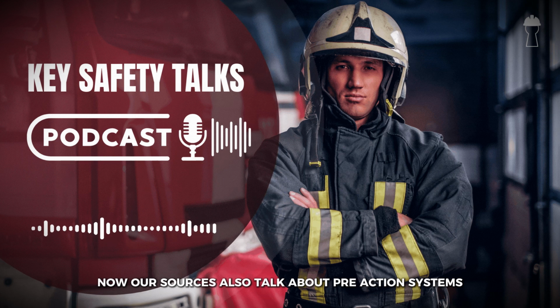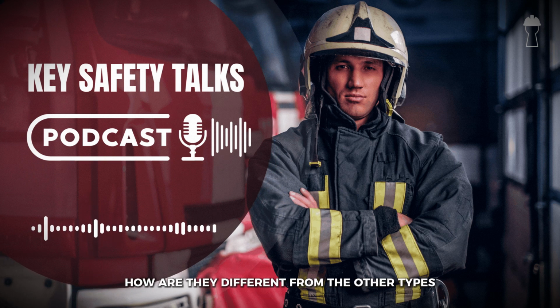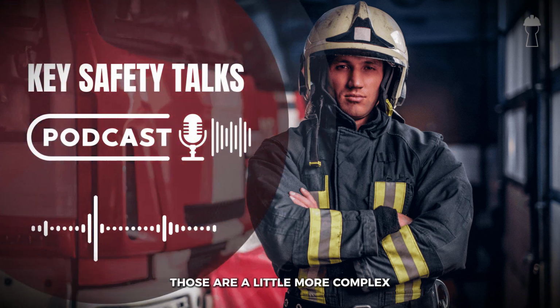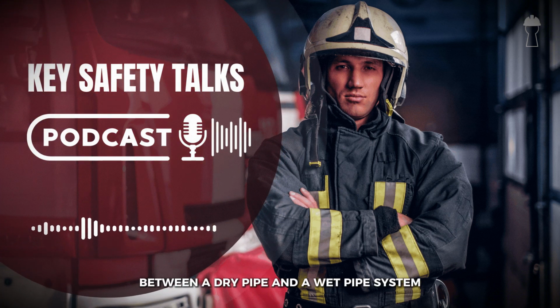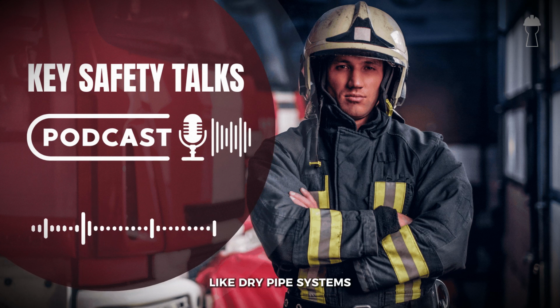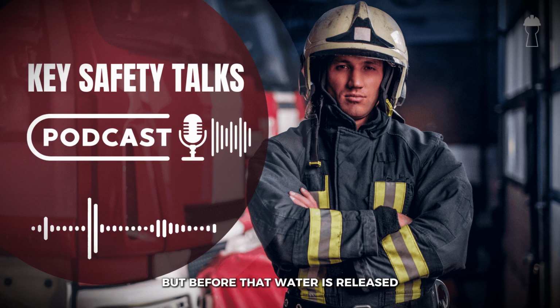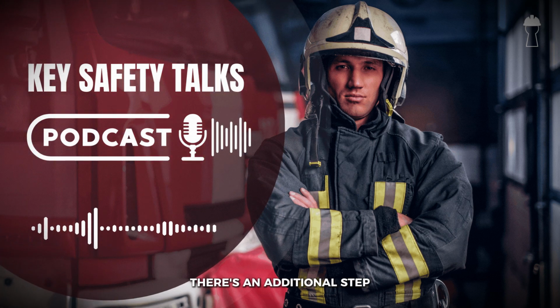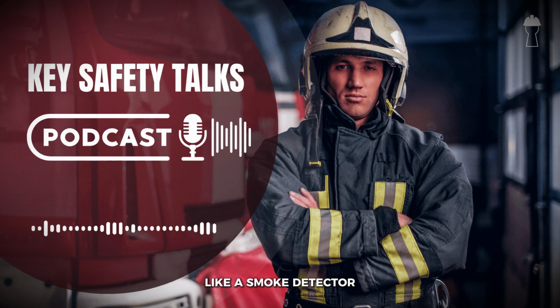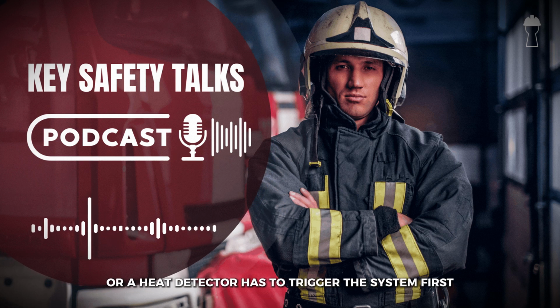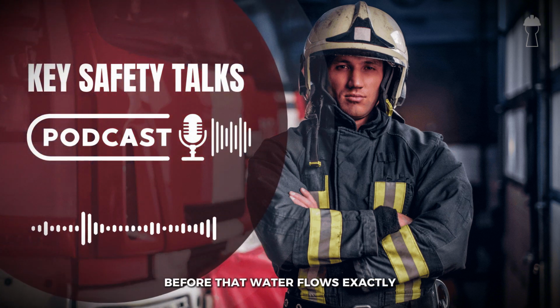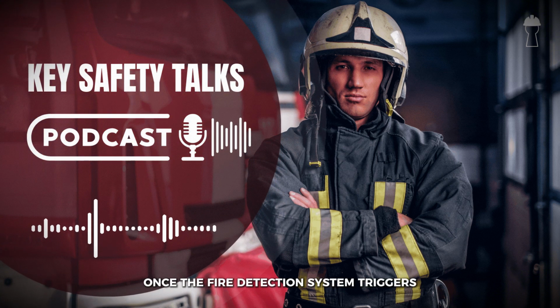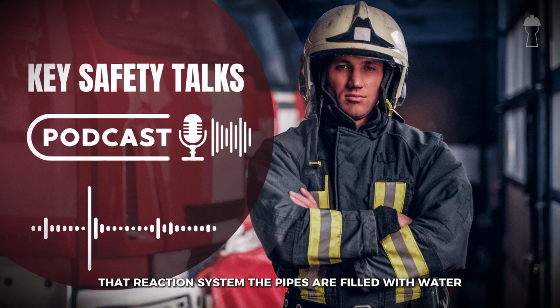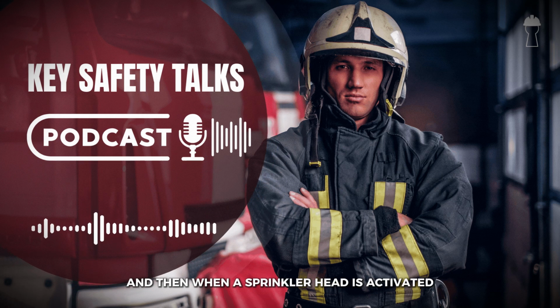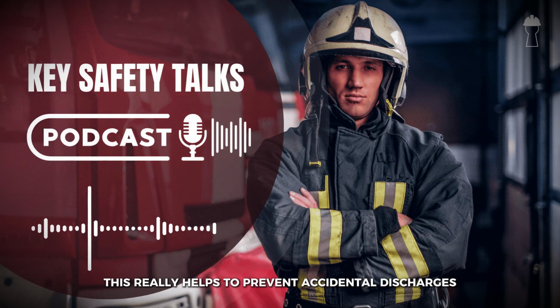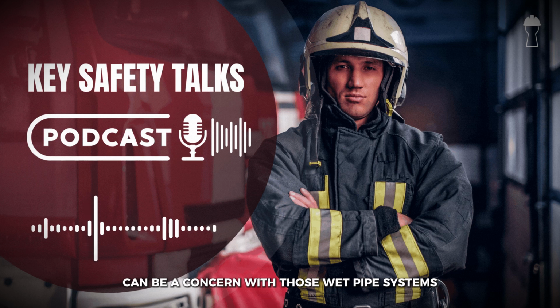Now, our sources also talk about pre-action systems. How are they different from the other types we've talked about? Pre-action systems, those are a little more complex. They're kind of a hybrid between a dry pipe and a wet pipe system. Like dry pipe systems, the pipes aren't initially filled with water, but before that water is released, there's an additional step. Usually, a fire detection system like a smoke detector or a heat detector has to trigger the system first. So there's like an extra layer of verification before that water flows. Exactly. Once the fire detection system triggers that pre-action system, the pipes are filled with water, and then when a sprinkler head is activated, the water is released. This really helps to prevent accidental discharges, which can be a concern with those wet pipe systems.